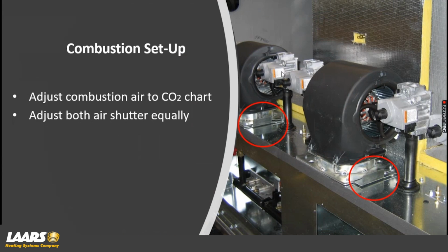So once the gas valves are all adjusted to 2.5 inches, what's left is your combustion air. And all you're going to do is adjust an air shutter. And you're going to close the cover door afterwards once you make an air shutter adjustment. Why? Because, especially if you're ducted, you know, 500,000 BTU boiler, you might have a 6-inch collar and you're ducting 50 feet with 3 elbows for combustion air. That's a vent restriction. With the cover off, you're just pulling combustion air right into the blower and down into the chamber. So you want that extra restriction, especially if it's ducted.